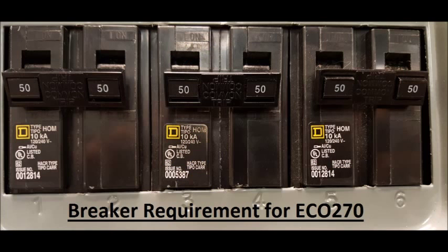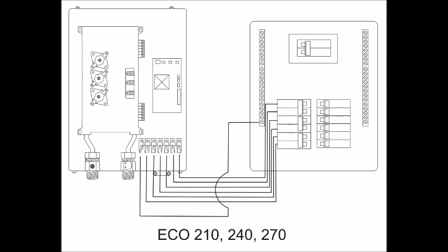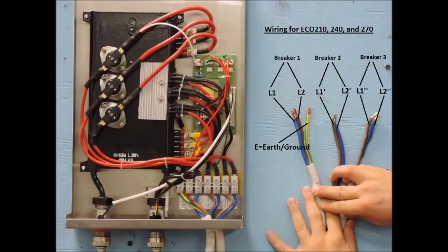Lastly, our eco-270 unit runs on three 220V double pole 50A breakers, meaning the unit has access to 150A. This unit will wire up the same as the eco-210 and 240, only it will be using a breaker with a higher amp limit.